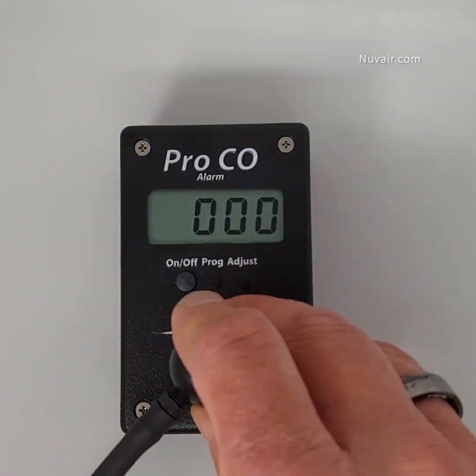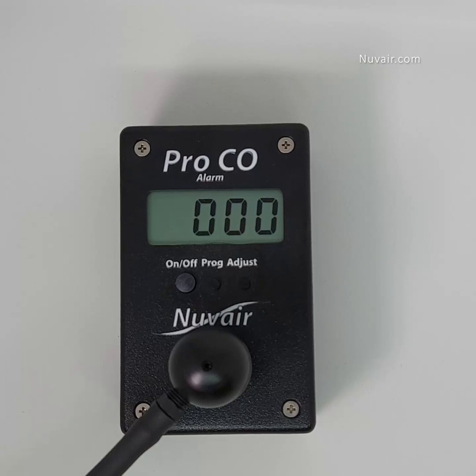Gas flow to the analyzer should be regulated to 0.5 to 5 liters per minute, with no pressure on the sensor. Pressurizing the sensor will lead to inaccurate readings and could damage it. If using a Nuvair flow reducer, the incoming pressure should be between 75 and 150 psi.